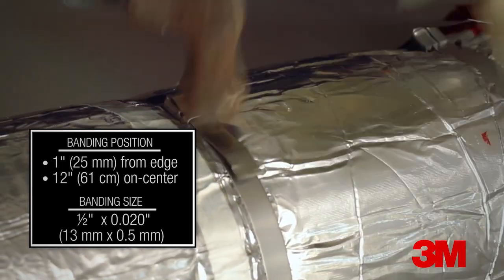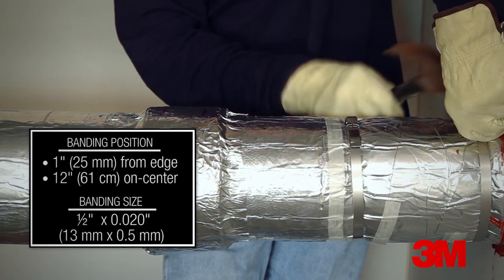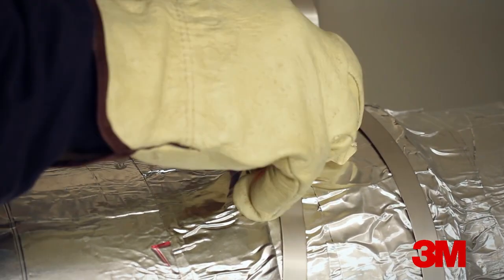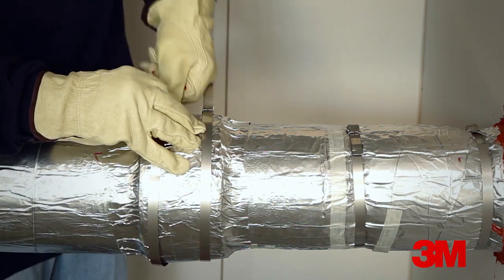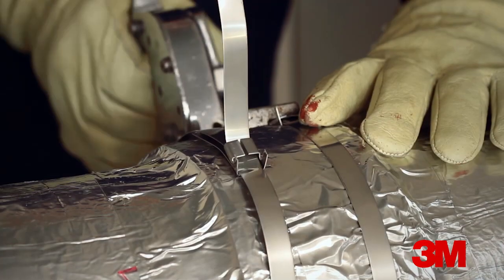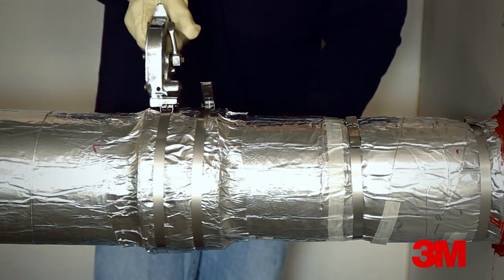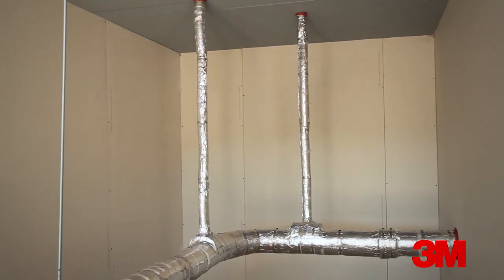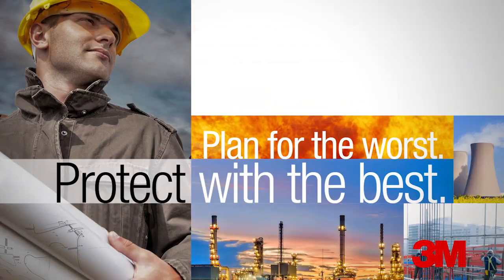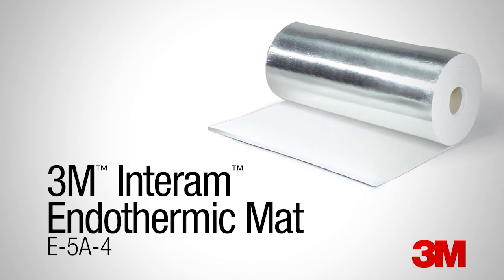The typical band sizing is a minimum ½ inch or 13 millimeters wide by 0.020 inches or 0.5 millimeters thick. Check the individual design listing for banding width and thickness. The bands are passed through wing seals and tightened with a band tensioner, then the wing seals are closed. Note that if band tightening affects the sealant at the EMAT assembly interface, additional sealant should be applied and tooled into place. When collars are used, they require banding at both edges spaced approximately 1 inch or 25 millimeters from the edges. Plan for the worst. Protect with the best. 3M Interam Endothermic Mat E-5A4 for protection of critical electrical circuits.